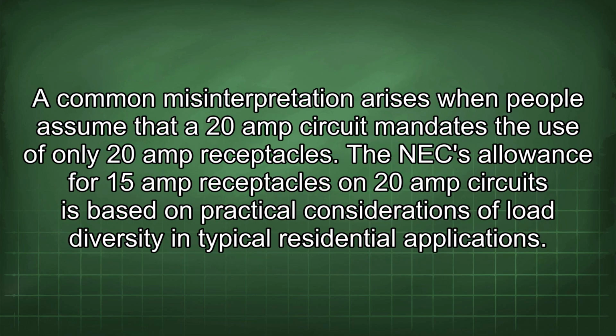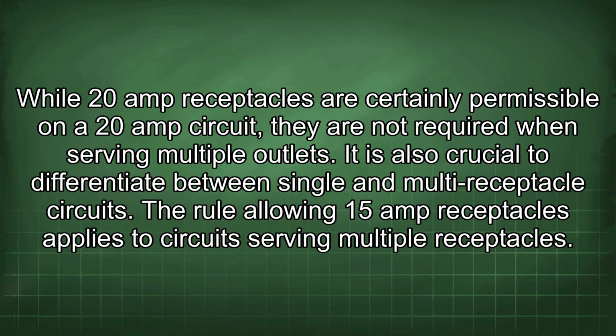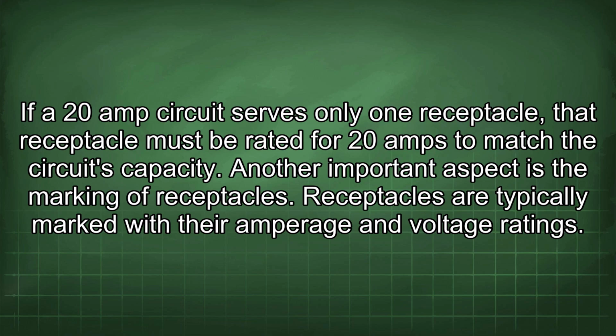A common misinterpretation arises when people assume that a 20 amp circuit mandates the use of only 20 amp receptacles. The NEC allowance for 15 amp receptacles on 20 amp circuits is based on practical considerations of load diversity in typical residential applications. While 20 amp receptacles are certainly permissible on a 20 amp circuit, they are not required when serving multiple outlets. It is also crucial to differentiate between single and multi-receptacle circuits. The rule allowing 15 amp receptacles applies to circuits serving multiple receptacles. If a 20 amp circuit serves only one receptacle, the receptacle must be rated for 20 amps to match the circuit's capacity.